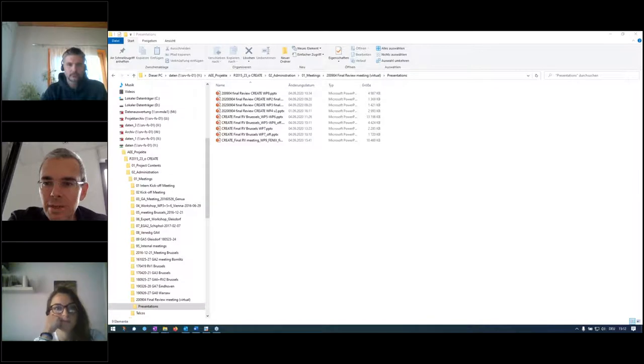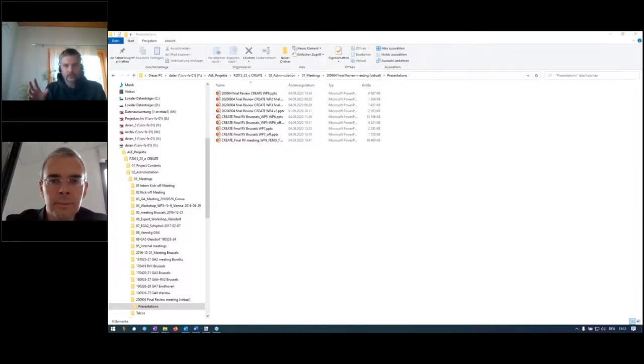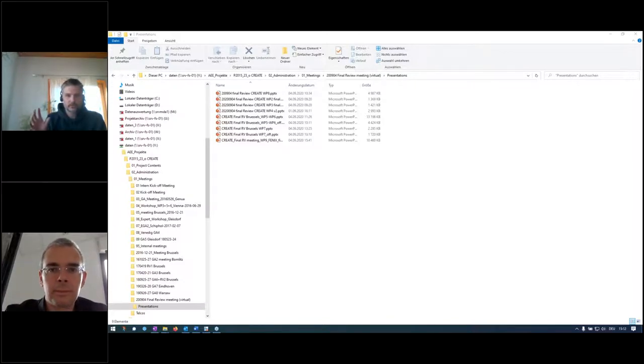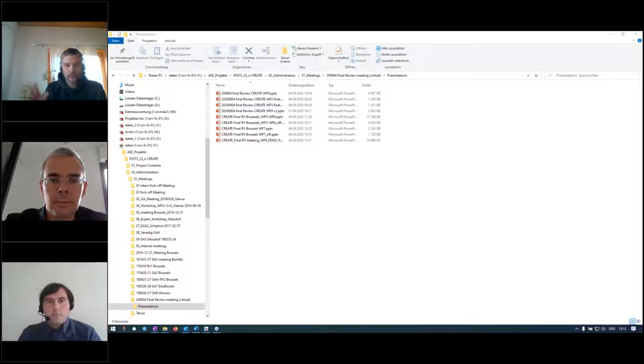The question is: is the borehole length higher in the CREATE concept compared to what you would need in a conventional ground source heat pump? In our case, not now, because the heat pump has a higher peak power, so a higher extraction power from the ground source - so it was more or less the same. So the answer is no. Okay, clear, thank you very much.